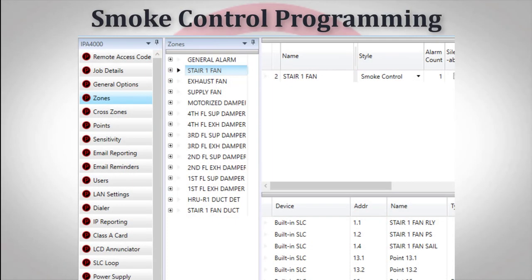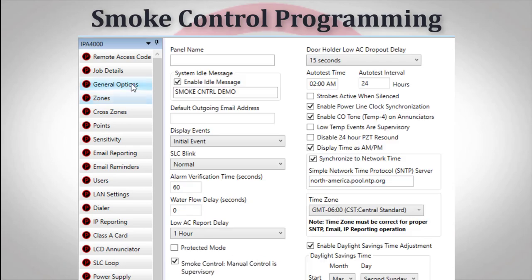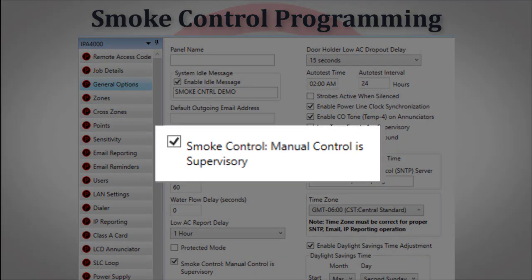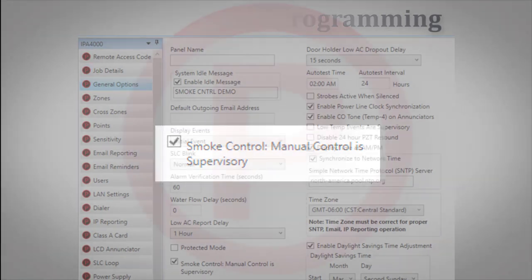Once a smoke control style zone has been added to a program, a new option will appear under the general options tab of the software. Smoke control manual control is supervisory will automatically be checked, meaning that activating any of the manual control switches will enunciate a supervisory condition on the fire panel.